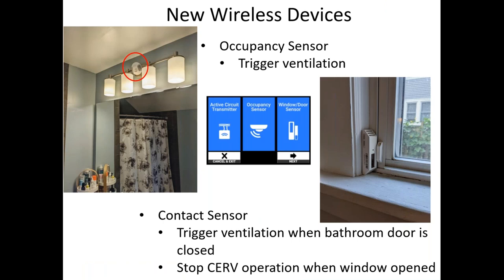So some new wireless devices we've released are an occupancy sensor. This wireless sensor can be used to trigger ventilation. So you may have several of these in one location. You may have a wall switch along with an occupancy sensor, along with a humidity sensor, and any of those could trigger ventilation in the CERV, but maybe for different reasons.